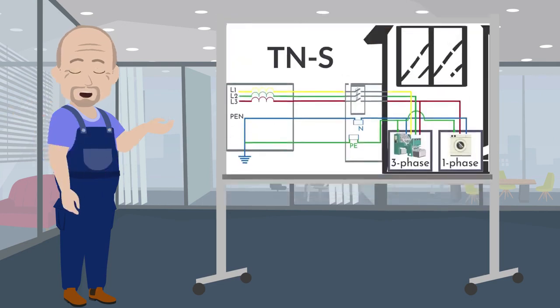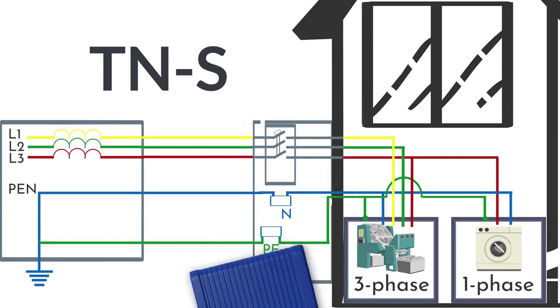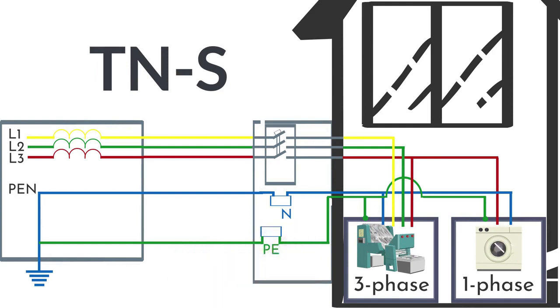Now let's talk about the TNS system. It is the safest power supply system, where zero protective and zero working conductors are separated along the whole length of the circuit, since the separation of two neutrals is carried out in the transformer substation. Three-phase voltage is supplied via five wires, while single-phase voltage is supplied by three wires.